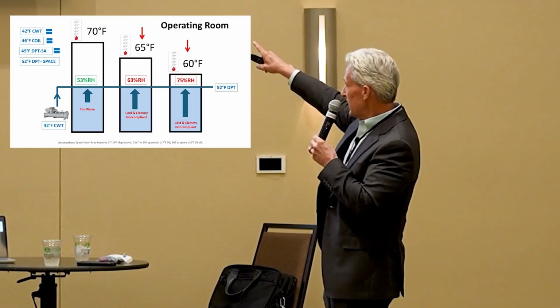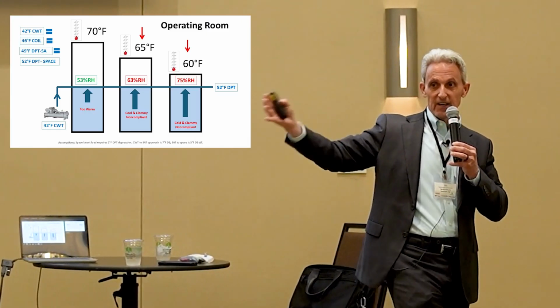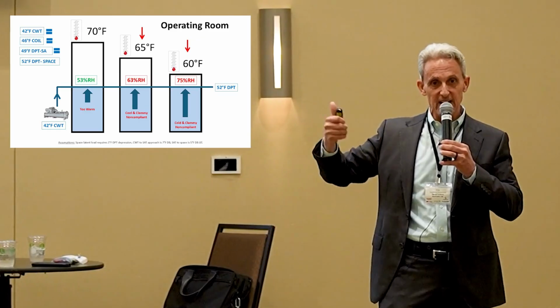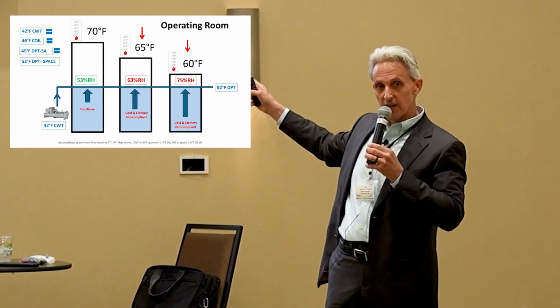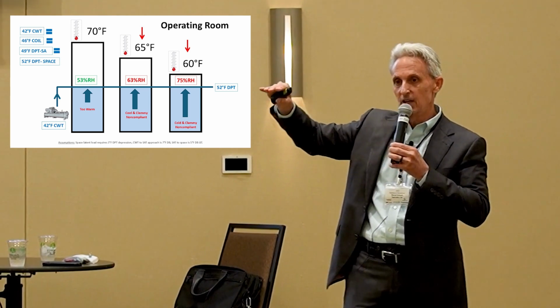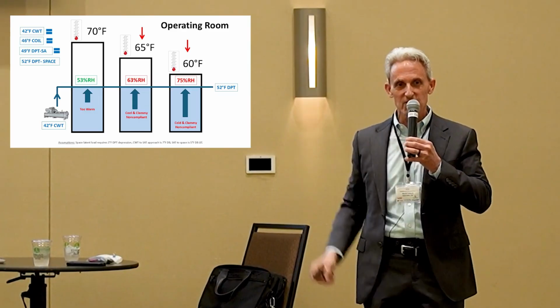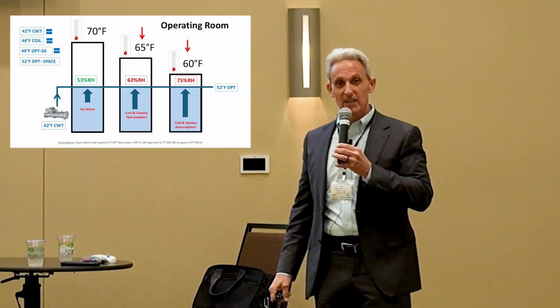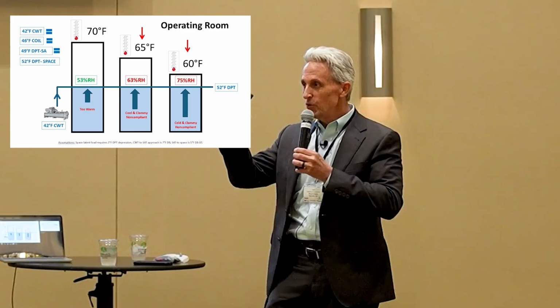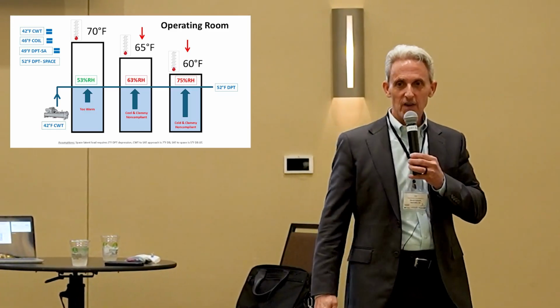And just an inkling of humidity excursion. Let's say it rains outside and excess humid air gets into the system and my system isn't designed to handle it. And I'm chugging along at this and all of a sudden the humidity goes 75, 76, 80, 85. What happens from above? We're sent this little message. You're messing with Mother Nature. We condense moisture. We form dew on those cold surfaces and it rains in the OR, right?